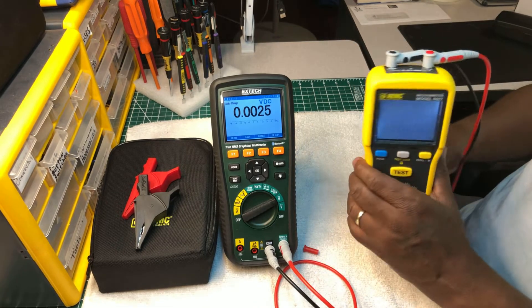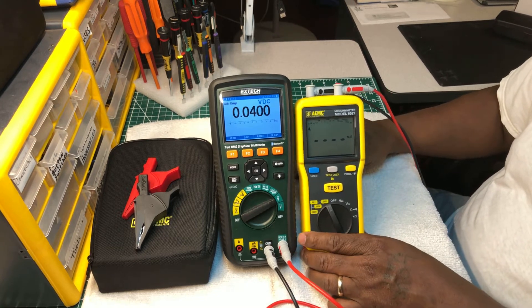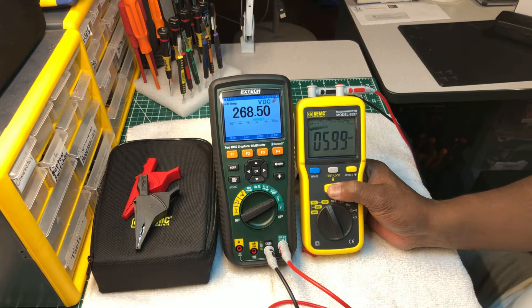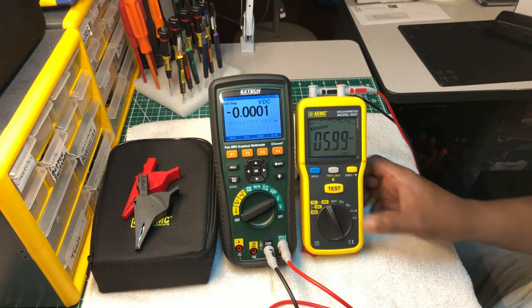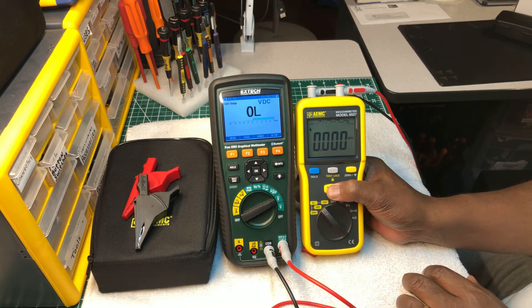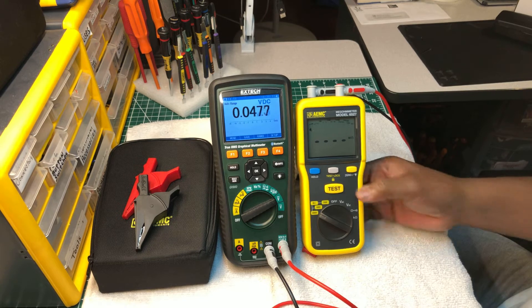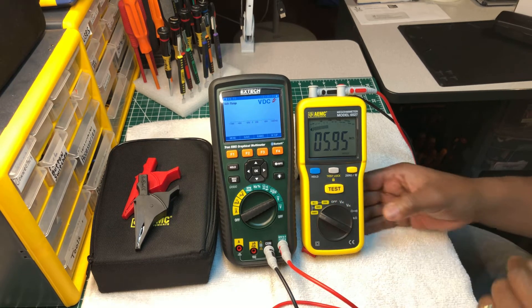Let me do some tests right here and show you guys the test ranges it's putting out. Starting at 250 volts — it's putting out 268 volts, 5.9 megaohms — so about six megaohms. At 500 volts it reads 523 — that's good. At 1000 volts it reads 1033 volts with an impedance of 5.6 megaohms from the meter.